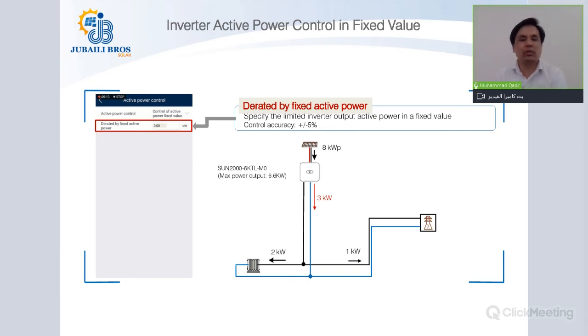So in the scenario shown on the screen, you can see that the 6 kilowatt inverter has been configured to provide a maximum of 3 kilowatt, even though it is capable of generating more than 3 kilowatt. The inverter is limited by the active power control as a fixed value of 3 kilowatt. So 3 kilowatt will be generated, and if that meets the requirement of the load, it will provide that to the load, and the excess will go towards the grid side. So this is how you will do the derated power control based on a fixed value in FusionSolar.